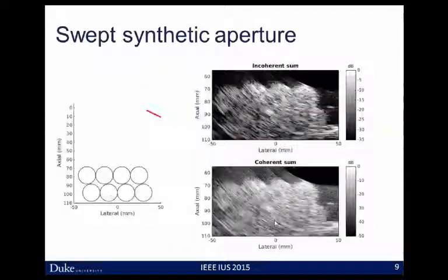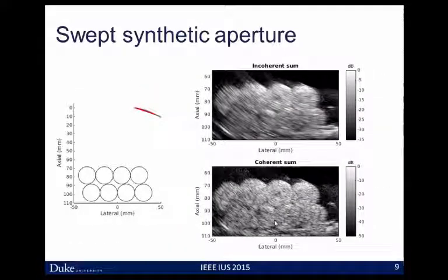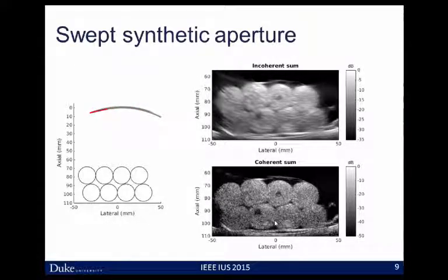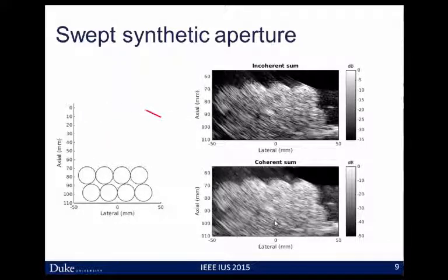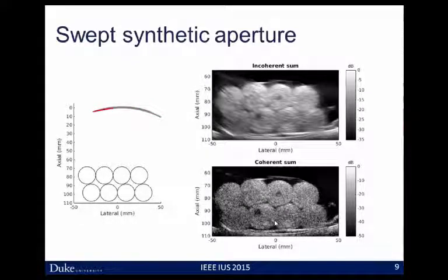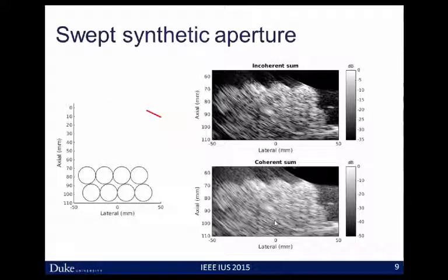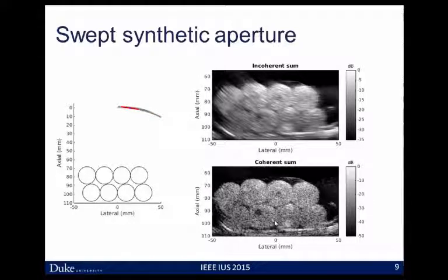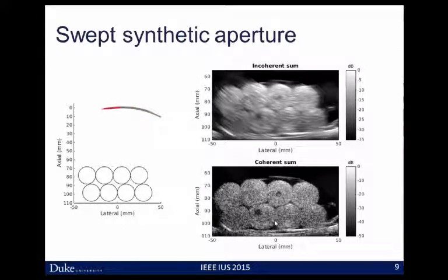To combine that data, we have two options. We can do it incoherently — the typical speckle compounding approach — where we see nice smoothing of that speckle texture as we add more frames with phase-insensitive data. But because we've precisely aligned our data to sub-wavelength precision, we can coherently sum it and build up a synthetic aperture giving us the full range of that 10-centimeter effective array. We can watch as that speckle pattern gets tighter, edge resolution gets better, and we'll quantify this further.